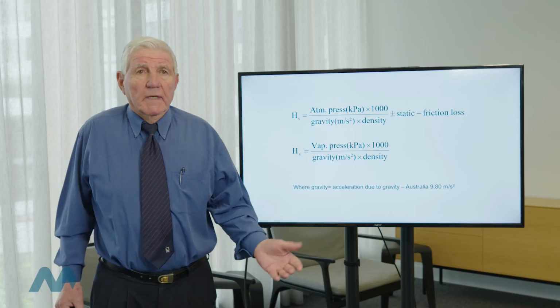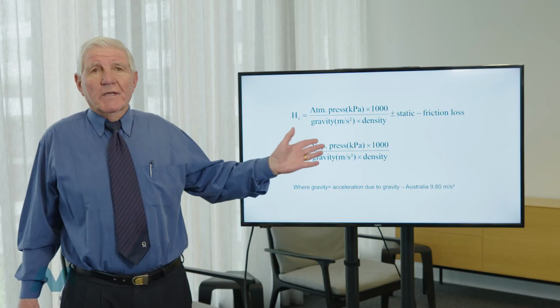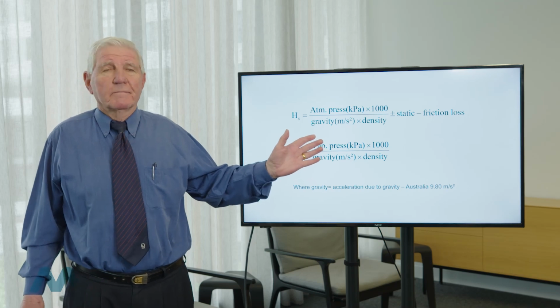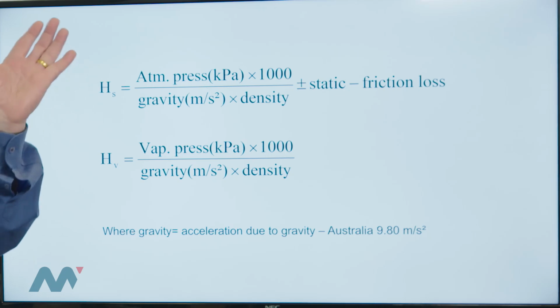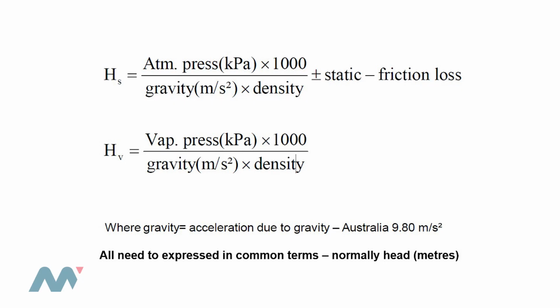You can only do the calculation. That calculation is relatively simple. I mean, it's not rocket science. So if you know where the cooling tower is, and you know where the pump is, and you know what the static head situations are, the biggest problem with a cooling tower is more likely to be air entrainment, unless they've got good ways of stopping that air entrainment getting into the pump suction line. That, for me, in my experience, is a bigger problem than the actual positioning of the static head.